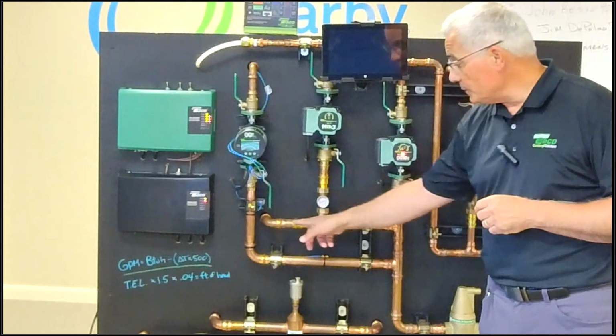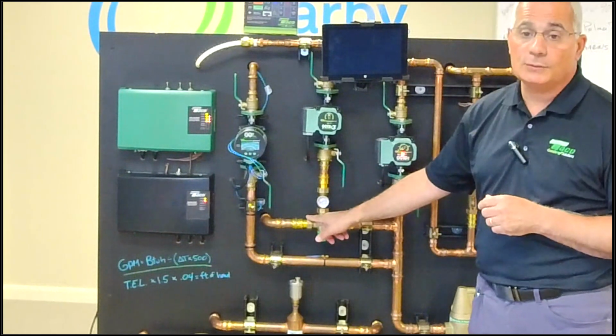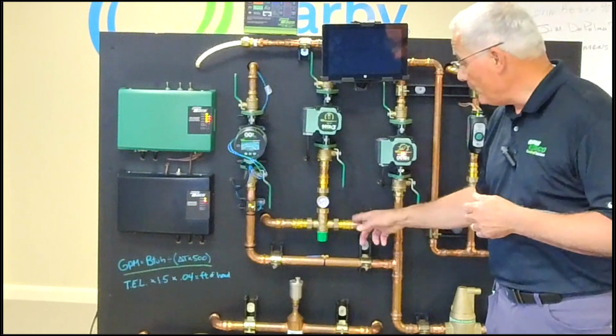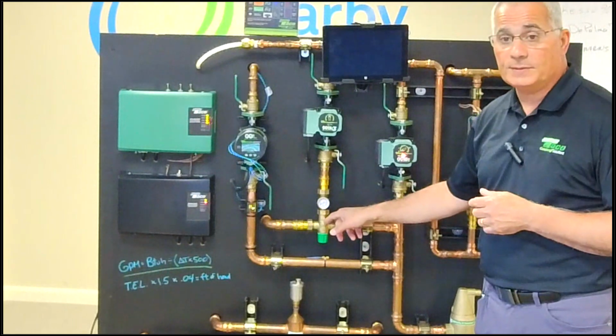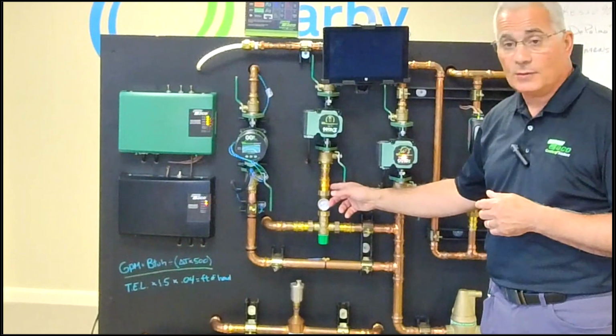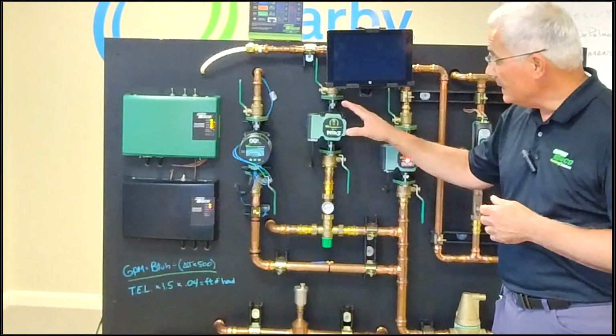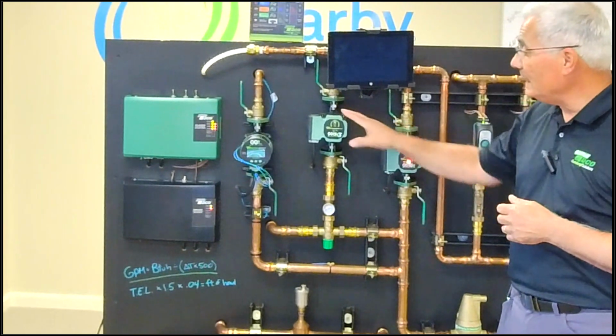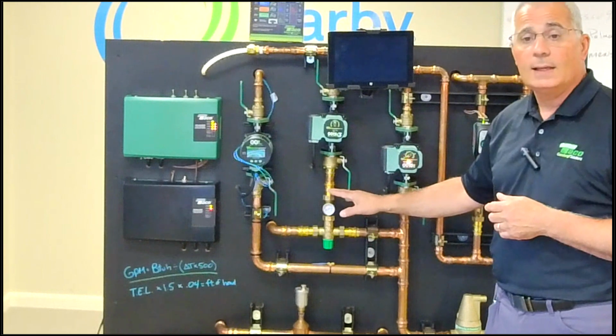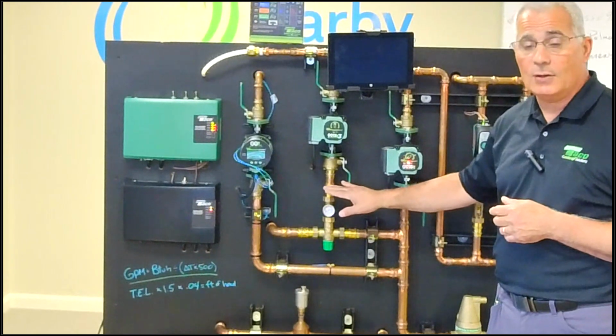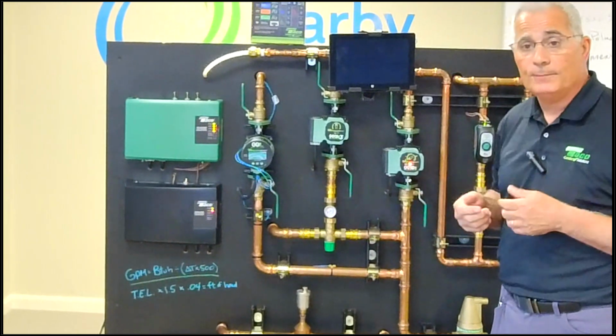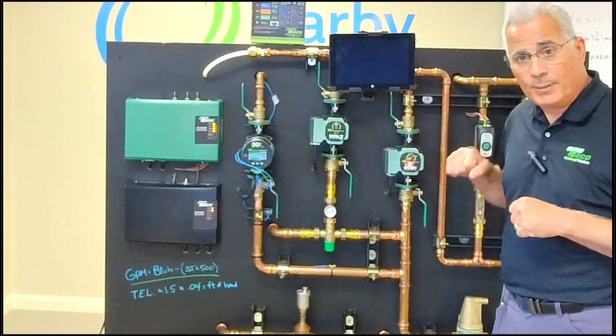So the cold return coming back, or colder return coming back, mixed with the incoming hot water from the system, is what's going to give us our mix temperature here. And the circulator for the radiant is always going to be on the mix side going out. We want to pull through mix valves. We never pump into them.